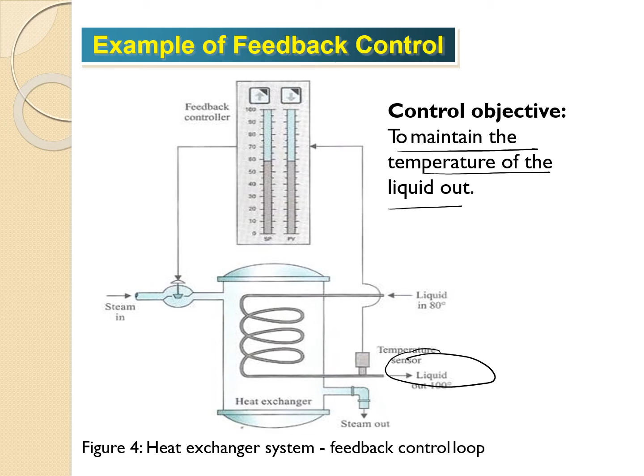Okay, so let's discuss. Now we have the control variable, which is our temperature of liquid out, and the manipulated variable is the steam flow rate, because we can see here there is an actuator connected at the steam in flow rate. So this actuator will regulate or manipulate the steam flow rate coming into the system. Okay, for the sensor, we have a temperature sensor here. It's used to measure the output temperature. This 100 degrees Celsius is our set point.